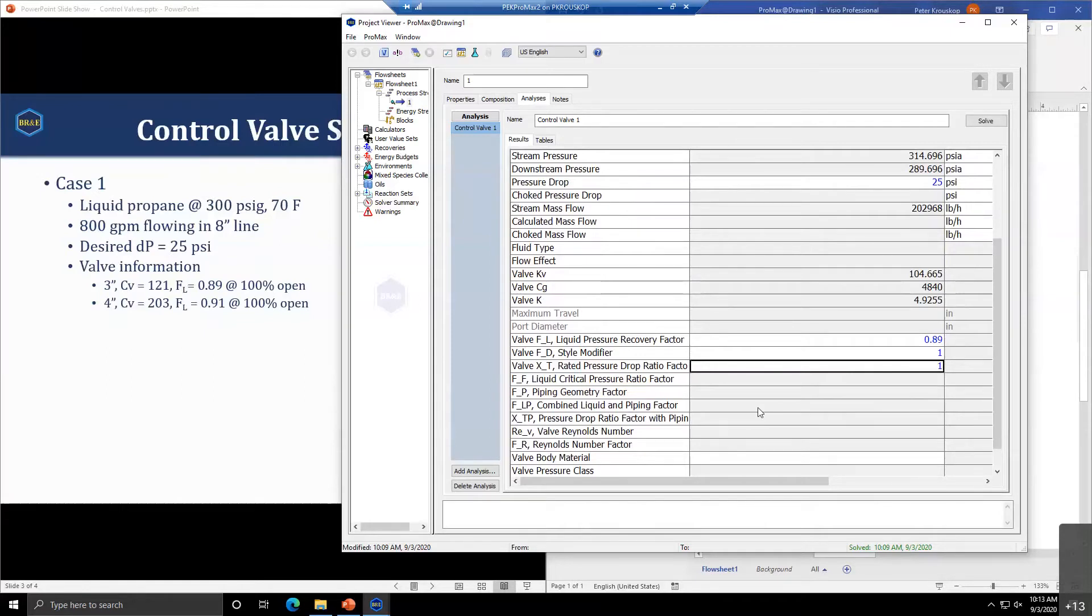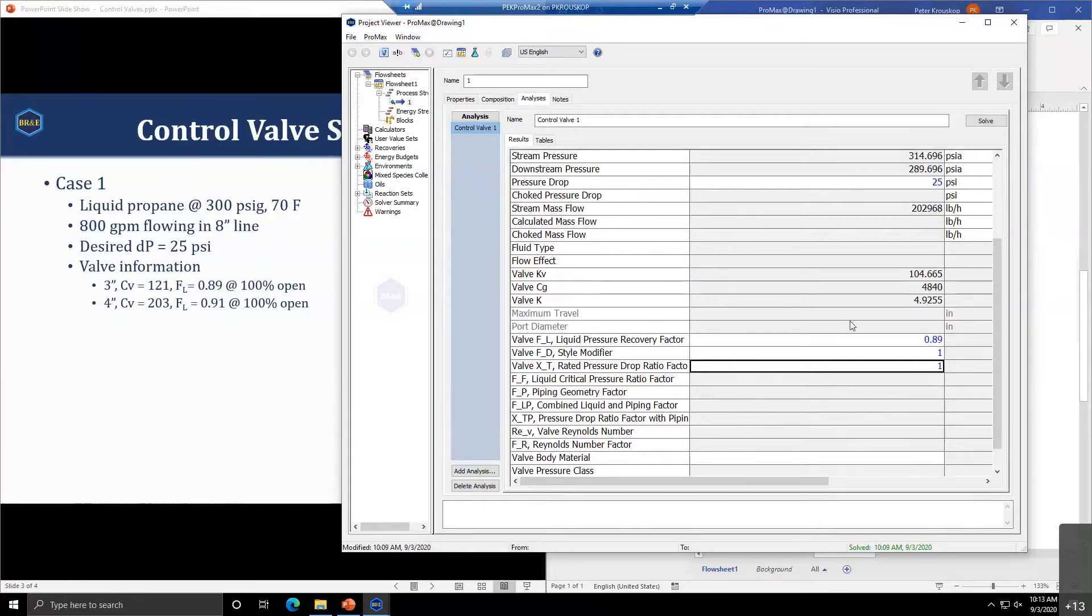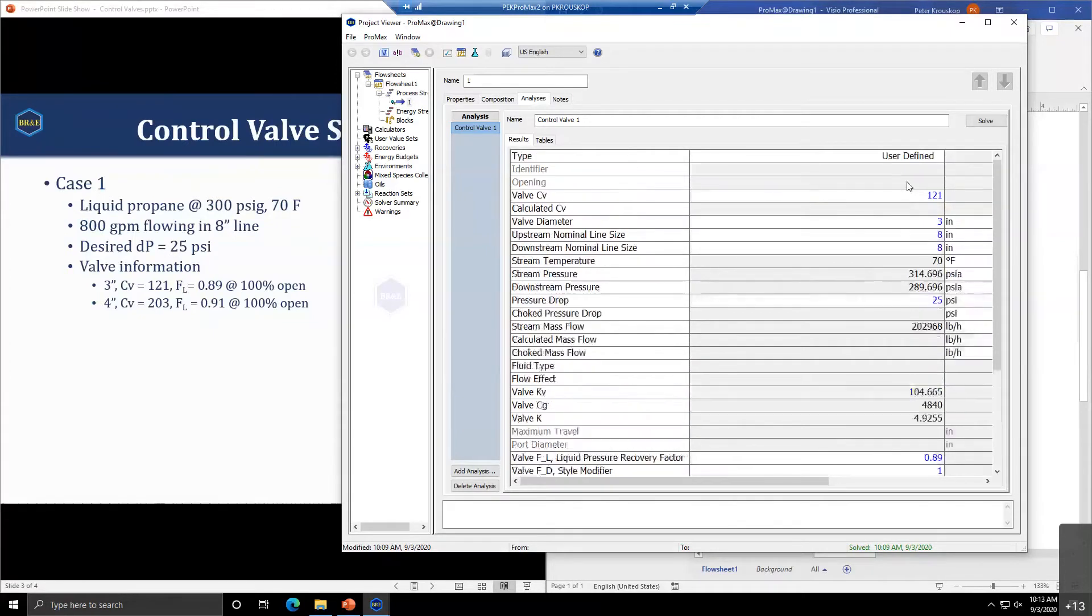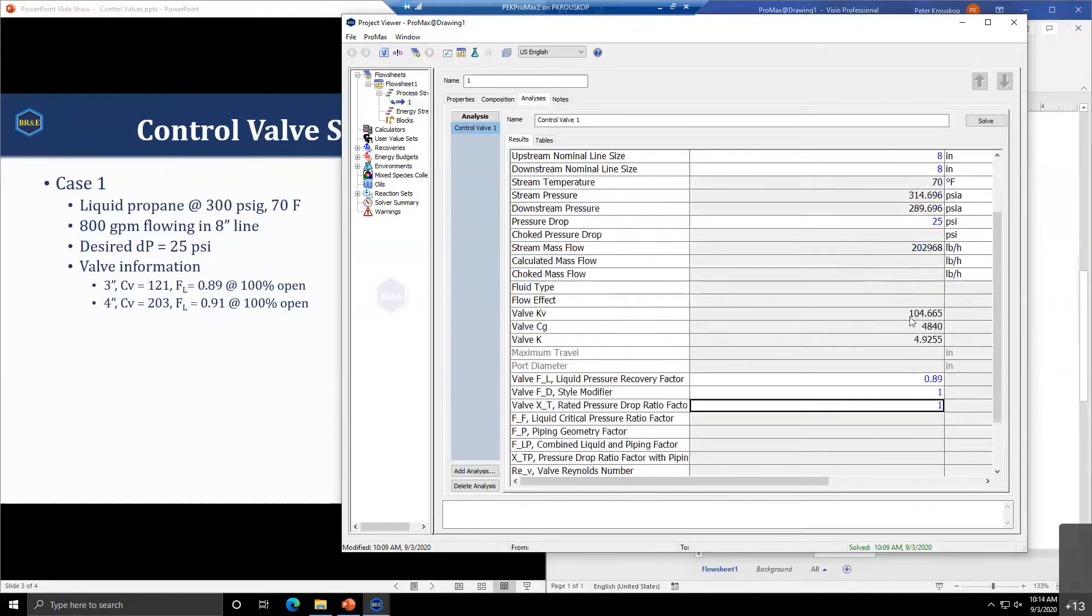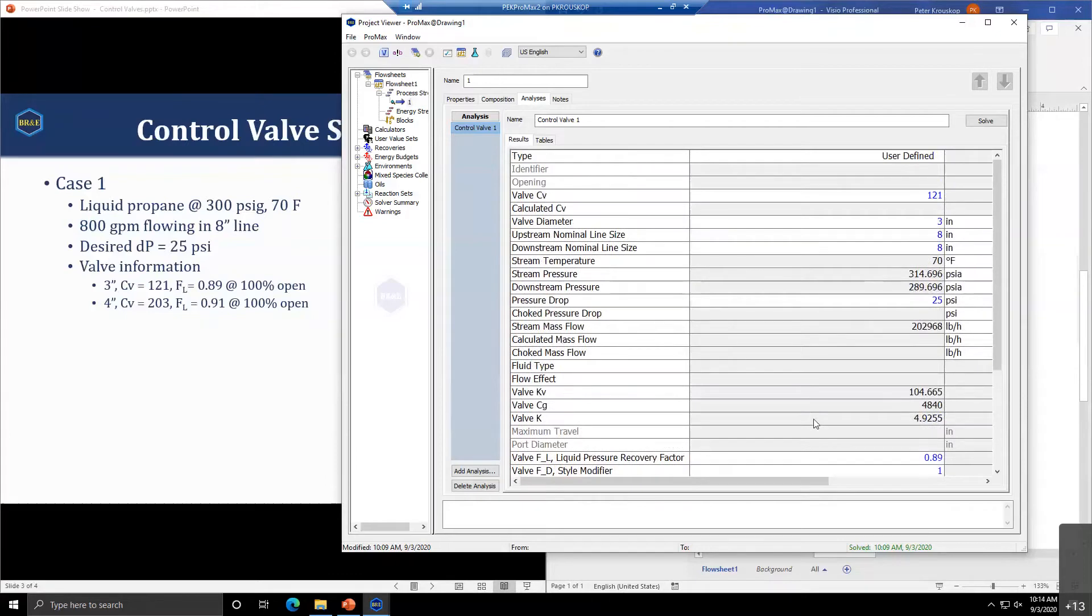We need to provide the style modifier FD. If you don't have that information, you can go with a value of 1. The style modifier is important if you're working with very viscous fluids or very low flow rates under non-turbulent conditions. The XT is important for vapor fluid. Since we have liquid, we can set this to 1.